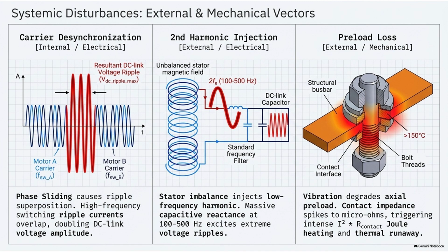Yep. Which brings us to the third mechanism. Right, because we've talked about high-frequency ripples, but this one introduces a completely different threat, the second harmonic ripple caused by motor imbalance. So in an ideal world, the three phases of alternating current running into a motor are perfectly balanced and symmetrical. Which means they sum to zero on the DC side of the inverter. In theory, yes, but physical reality is never perfect. Right, there's always friction or whatever. Exactly. A minor short circuit in the motor's stator windings, or slight unevenness in the mechanical bearings, or simply a temperature sensor drifting out of calibration. All of that can cause those three AC phases to become asymmetrical. Yes. And that physical imbalance feeds a massive low-frequency electrical ripple back into the DC link. We're talking about frequencies in the range of like 100 to 500 hertz.